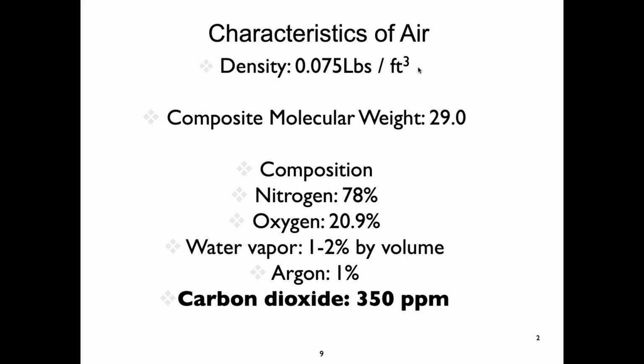How does that affect us? Well, one of the things we use CO2 levels for is determining how good the ventilation is in this space. If we weren't here and the air conditioning was running continuously, and 10% of the air was being exchanged with outside air all the time, and the CO2 level outside is 410 parts per million, what would it be in this room? Take a guess. No humans in here, nothing in here. The outside air is 410 parts per million. It's going to be the same thing. It's going to be 410 parts per million also, right?